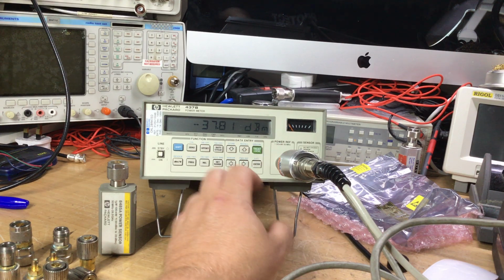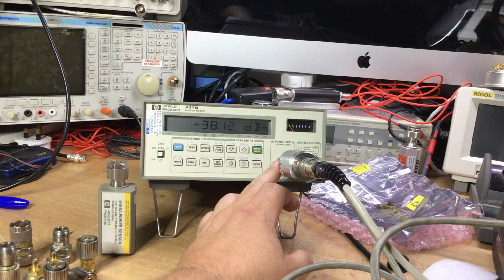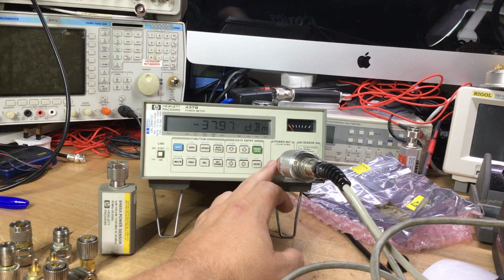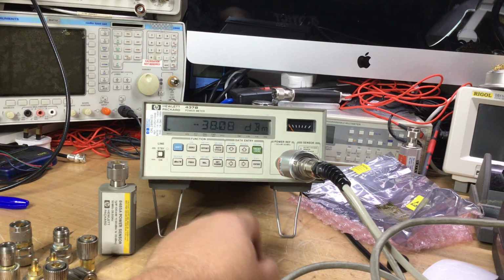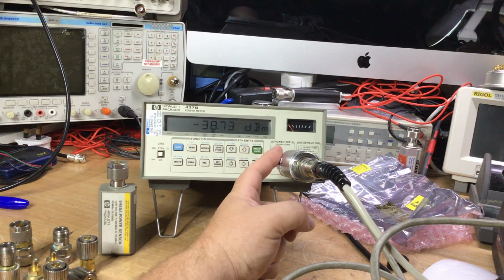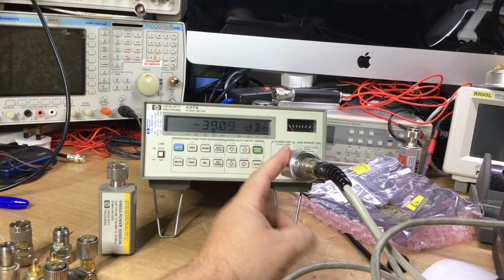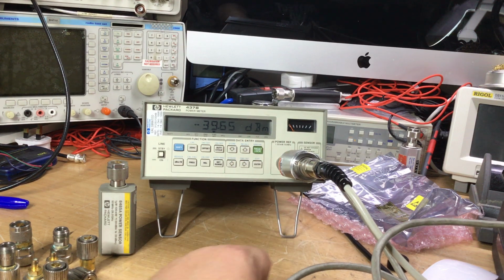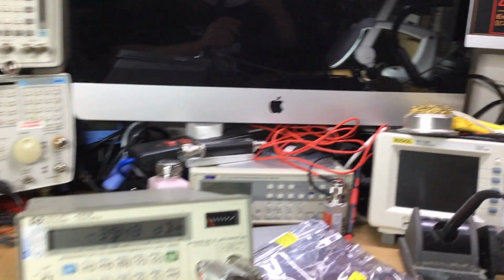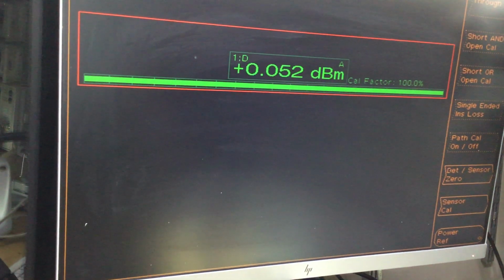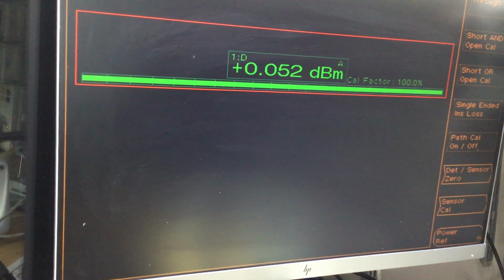So what we'll do now, we'll turn on the reference power on the meter by pressing shift and this button here. And now basically we've got output power from that port now entering this sensor for measurement. So what we can do now is go over to our Marconi power meter measurement in the microwave test set.